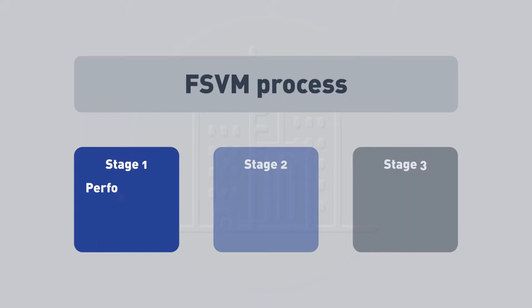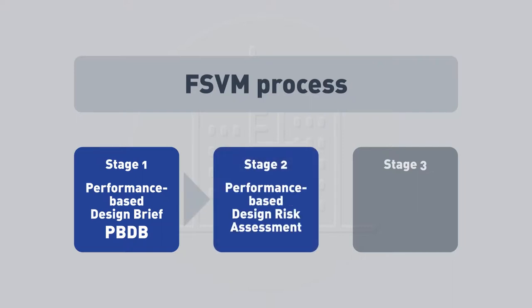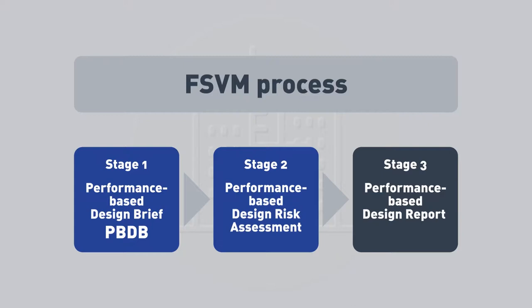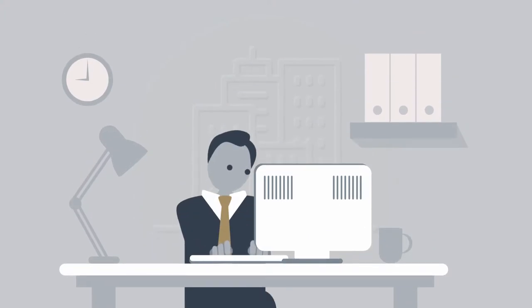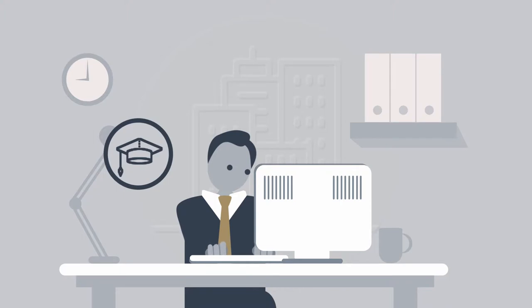The process for applying the verification method can be broken down into three key stages. The first stage is developing the Performance Based Design Brief, or PBDB, as outlined in part A2.24 of the governing requirements. The second stage is developing the performance based design risk assessment. These two stages are then combined to form the performance based design report — the third stage. The purpose of the report is to document how the proposed performance solution complies with the relevant fire safety performance requirements.